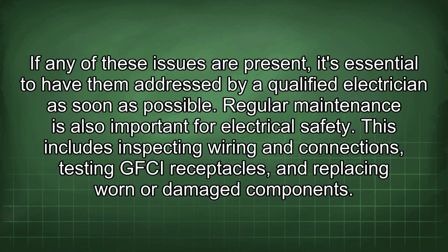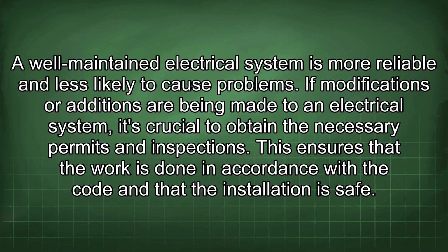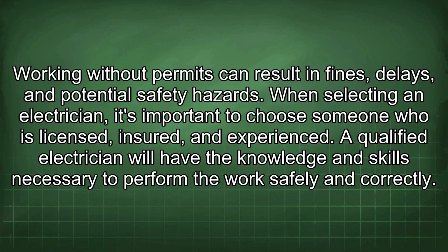This includes inspecting wiring and connections, testing GFCI receptacles, and replacing worn or damaged components. A well-maintained electrical system is more reliable and less likely to cause problems. If modifications or additions are being made to an electrical system, it's crucial to obtain the necessary permits and inspections. This ensures that the work is done in accordance with the code and that the installation is safe. Working without permits can result in fines, delays, and potential safety hazards.